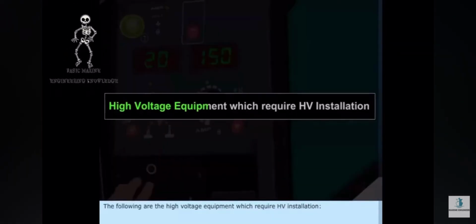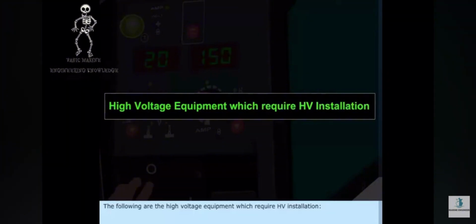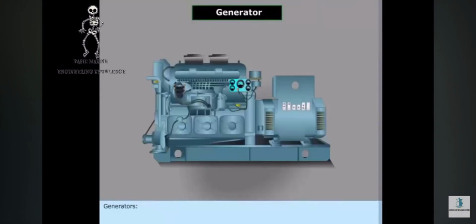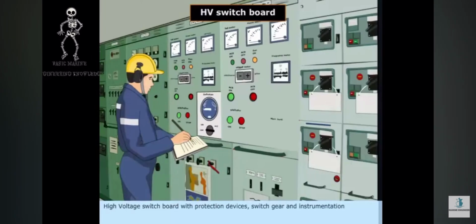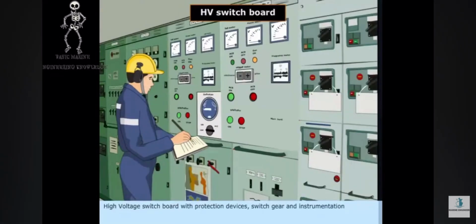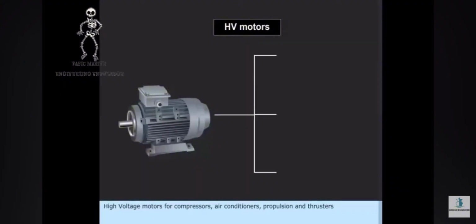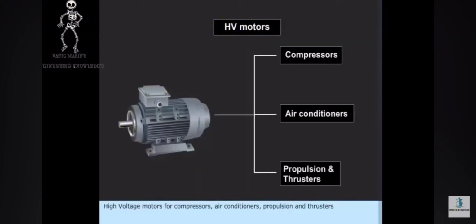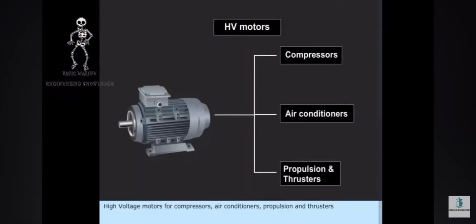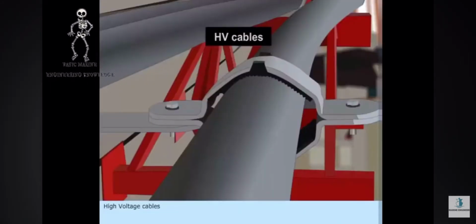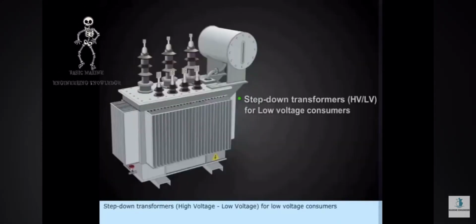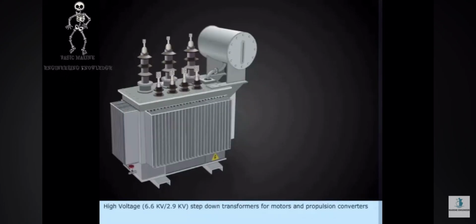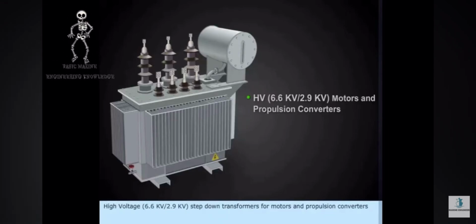Here are some equipment which requires high voltage installations. Generators, high voltage switchboards with protection devices, switchgear, and instrumentation. High voltage motors or compressors, air conditioners, propulsion, and thrusters. High voltage cables, and step-down transformers, high voltage to low voltage for low voltage consumers. High voltage 6.6 kV and 2.9 kV step-down transformers for motors and propulsion converters.